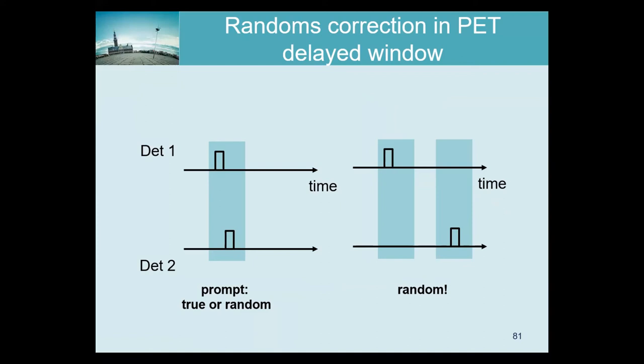This final slide is about randoms correction in PET. In PET we have problems with both randoms and scatter. Scatter is still a pain, but randoms can be estimated pretty accurately — they contribute noise but their effect on bias is negligible. Here is the basic idea: a detector sees a photon, and the system checks whether within the time window another detector has also seen something. If yes, the PET camera decides these two events are related and records a coincidence.